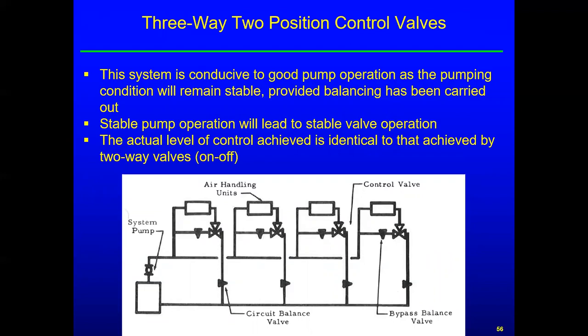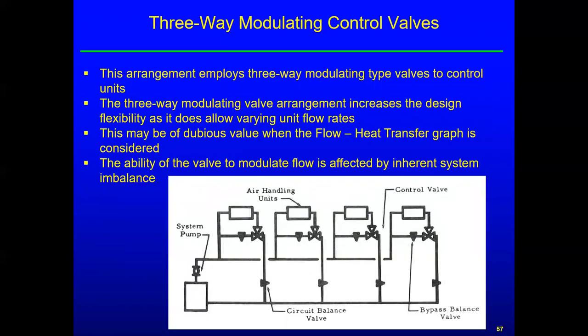Okay, so the three-way two-position control valves, it's conducive to good pump operation. We've said that because the pump doesn't know if it's set up correctly. So stable pump operation helps the control valves. And the actual level of control is identical to that of the two-way valves, because it's either full flow or no flow, whether you do it with two valves or however many valves you got. Okay, let's go on to three-way modulating control valves.